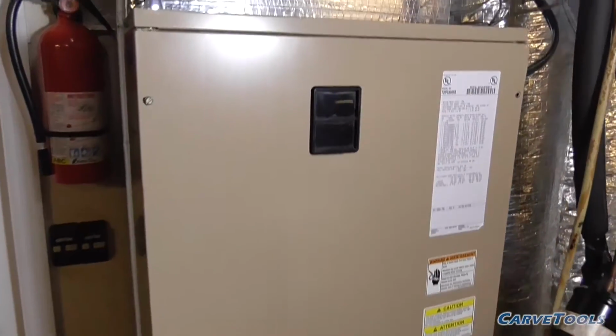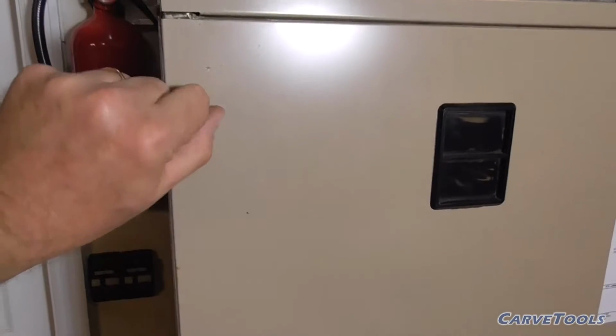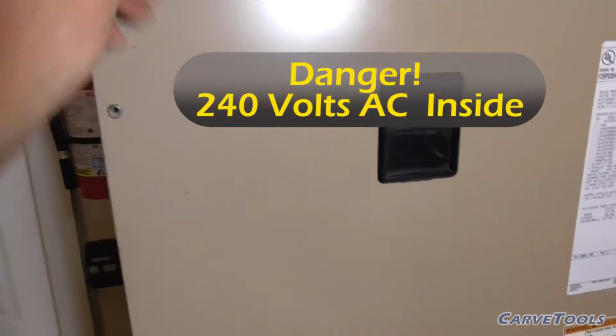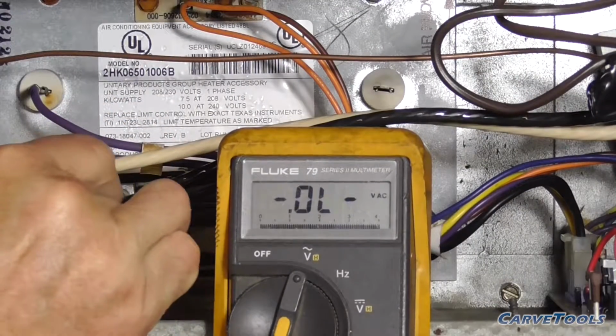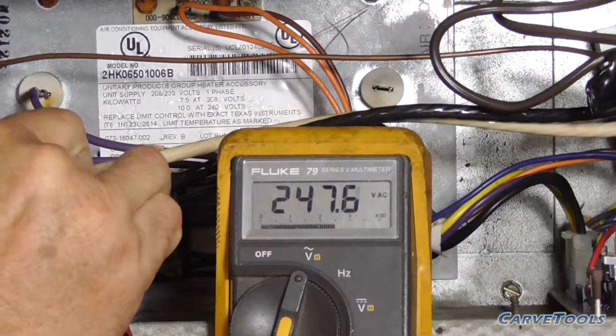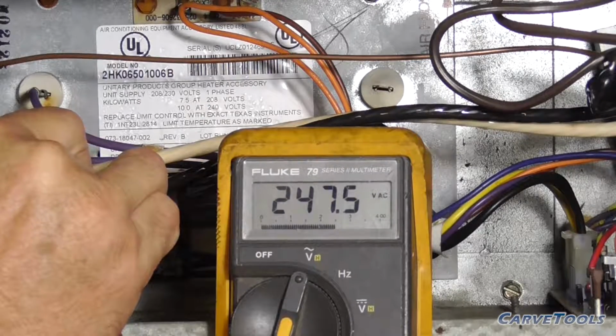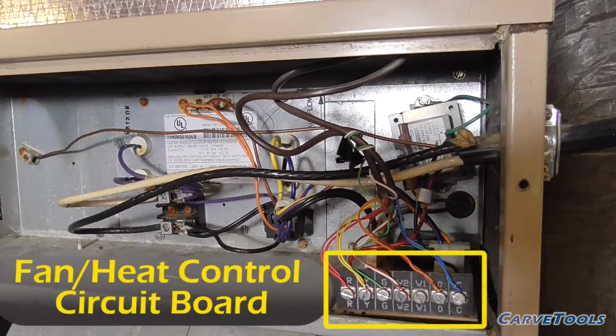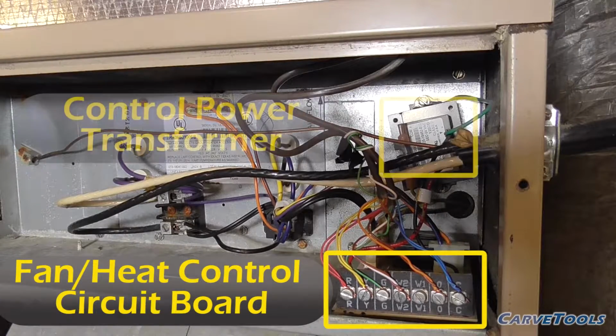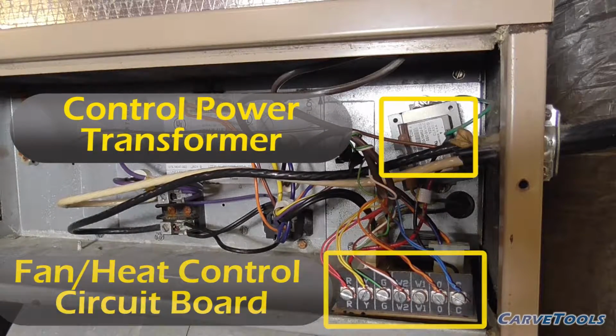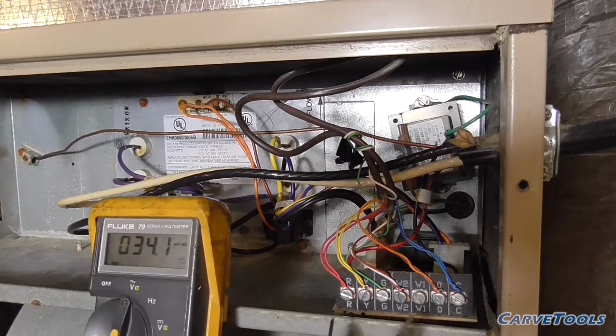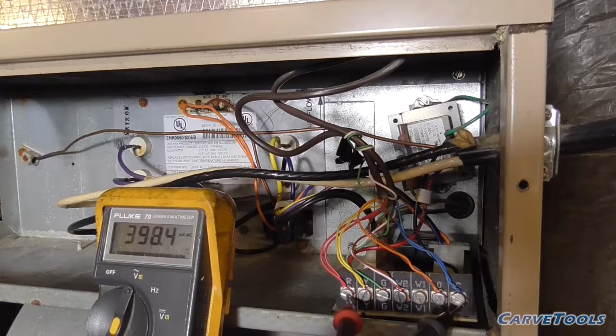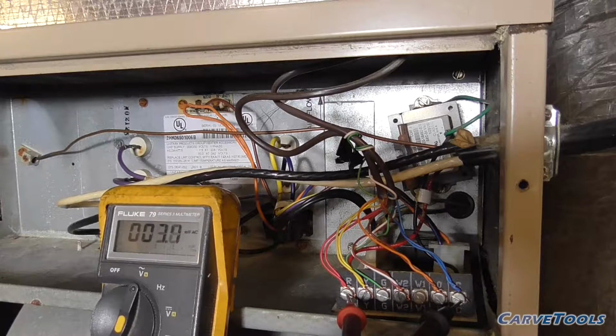The next step, I'm going to check the air handler unit inside. Now I'm removing the panel without turning off power. And I measure across the power terminals and it is 247 volts AC, so that's good. Inside the air handler is the fan and heat control board, and here is the control power transformer. I'm checking for 24 volts AC across the R and the C terminals, and there is nothing. Later in this video, I'll give you more detail about each terminal on the control board.